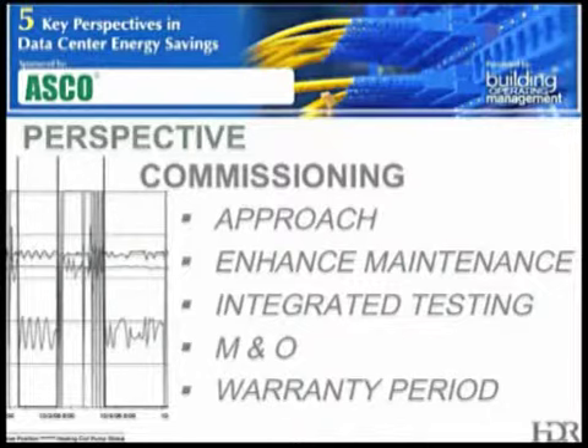And we also want to make sure we're not overcomplicating control strategies in the design process. During the functional and integrated testing phase, I feel one of the important things that often isn't talked about is let's establish a commissioning schedule for the project that requires pre-testing of systems, and let's make sure that the time necessary to pre-test and functionally test the systems, that we're not compromising the amount of time it takes our balancing teams to get in there and properly balance the hydronic and air systems. If we squeeze that subcontractor, we're likely to end up with a project that doesn't function the way we want it to.